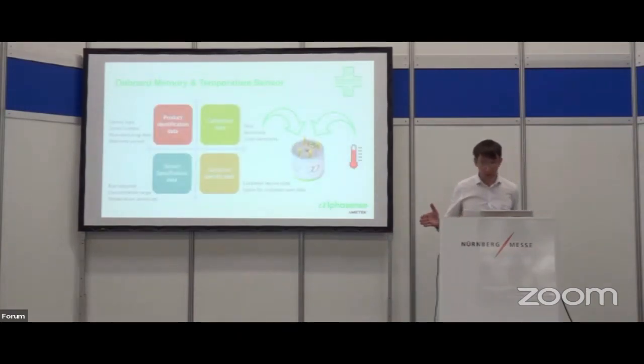What do we want to put in the memory? We have different fields of data. We want specific sensor information, including sensor type, serial number, manufacturing date, and warranty period. We want sensor specification data, general data like temperature compensation or the concentration range for that sensor, and calibration data, which is probably the main thing.